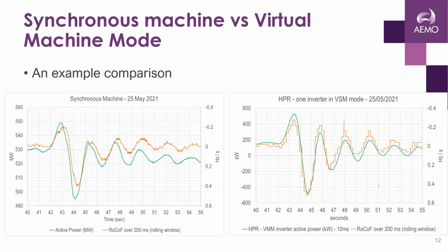This response is from one inverter only, compared against a roughly 550 or 600 megawatt synchronous machine. But when you scale that one inverter up to all inverters, it's likely that for the first one or two peaks you'll get a similar response. Now this response on the right-hand side is only in virtual synchronous machine mode, with no FFR enabled, so there's a caveat there.